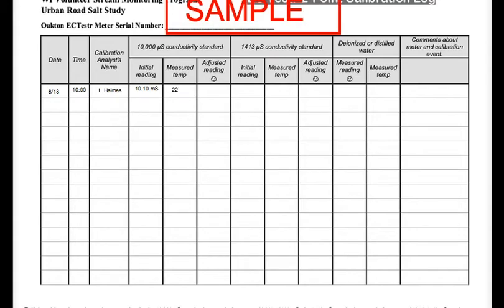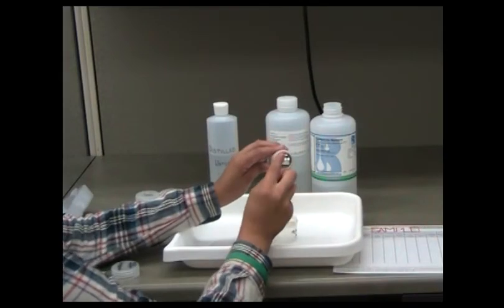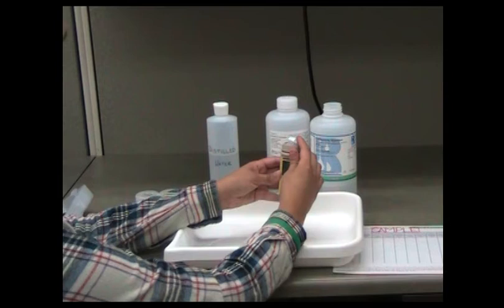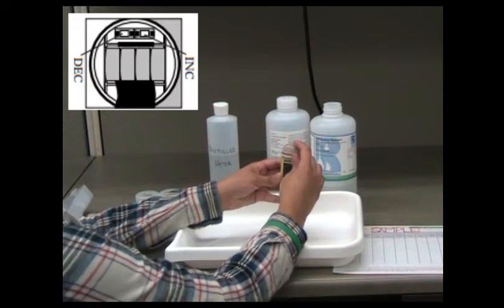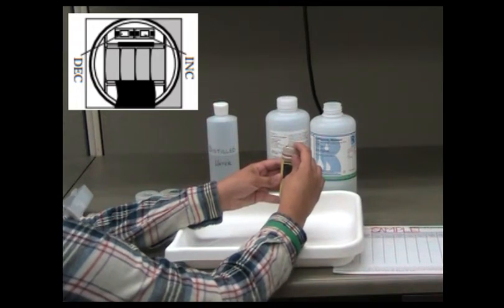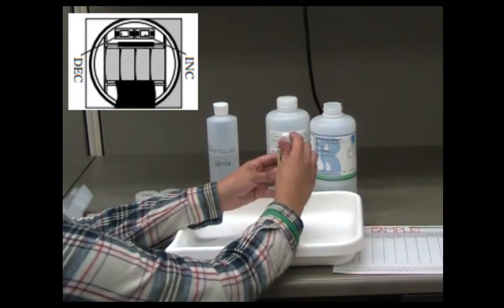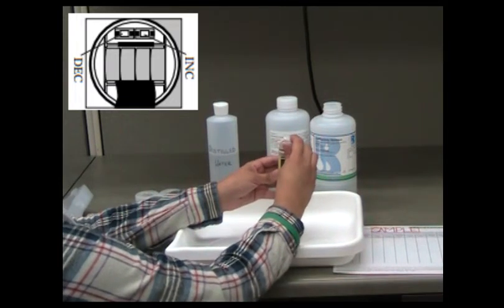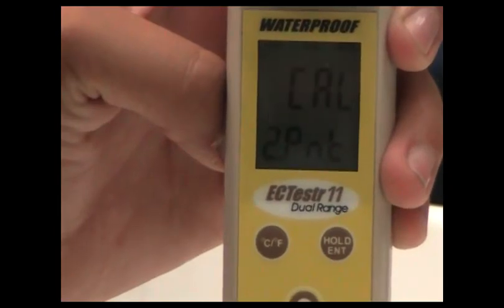Record the temperature on the calibration log. Keep the probe in the standard solution and press the increase button to enter calibration mode. The increase and decrease buttons are located behind the batteries. When the screen on the meter is facing you, the increase button is the one to the right and the decrease button is to the left. When you press the increase button, CAL should appear on the screen.